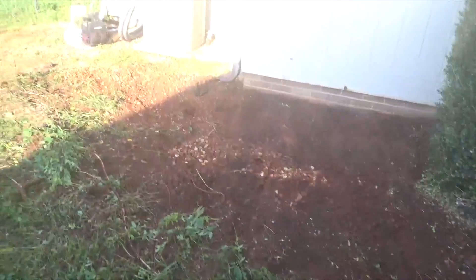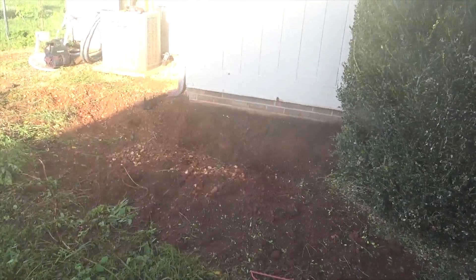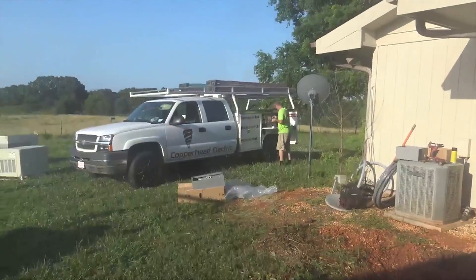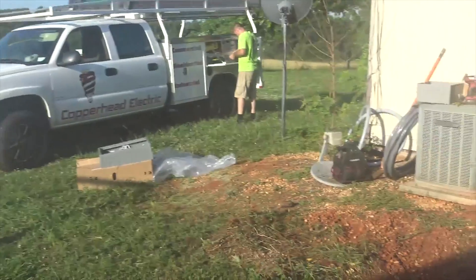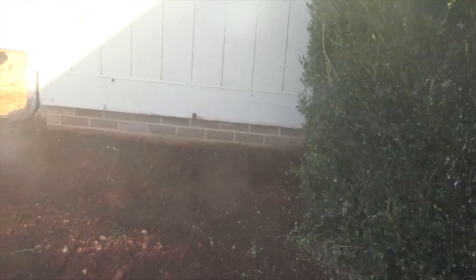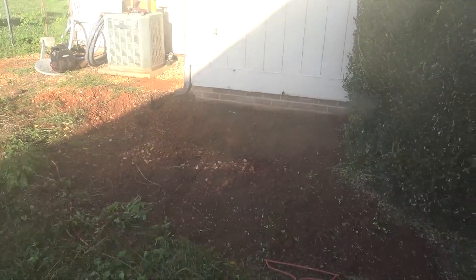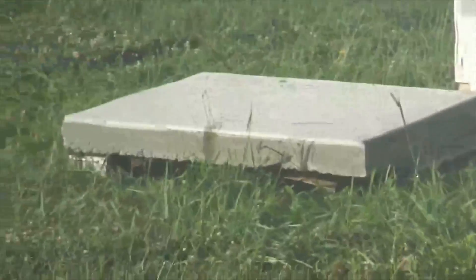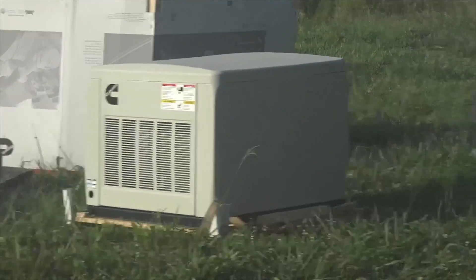Engineer 775, trying to beat the heat but here comes the sun — it's gonna be a very warm day as we install a new Cummins 20kW standby generator for this home. Larry is already getting started. Copperhead Electric is on site bright and early, determining where we're gonna put our transfer switch. We had to do a lot of ripping and tearing this morning of old bushes — landscape time — and got the pad leveled. I poured a pad at the house just to save some time, and then I'm gonna set the little Cummins on there and come up with our strategy. The meter base is here.